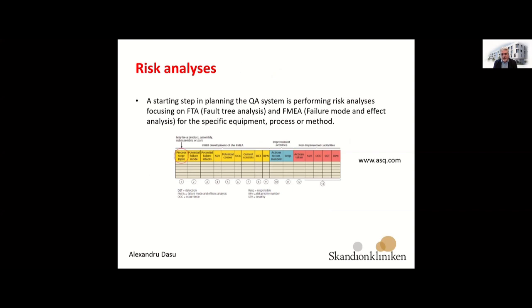So one important part of the quality system is a risk analysis. The risk analysis means performing an analysis of the possible failure modes, and also of their effects, for the specific equipment, process, and method that you want to use. This is an example of how such an analysis could be done according to the American Society for Quality, where you have a certain process, and then you think about potential failure modes. This is where experienced participants would think about how the system works, how the process works, what the steps and the influence factors in it are. And then they should think about what the potential effects are, what the causes are, and what controls could mitigate or minimize these causes, and so on.